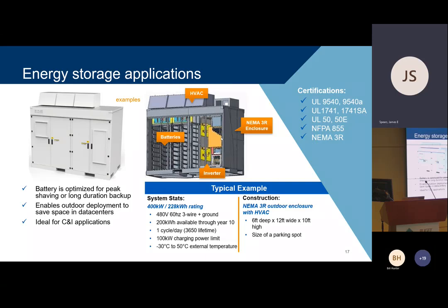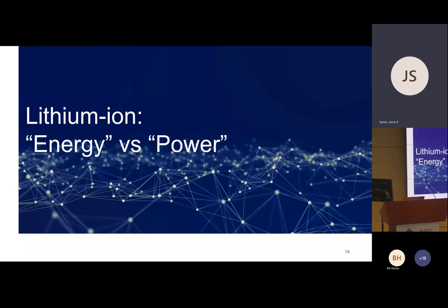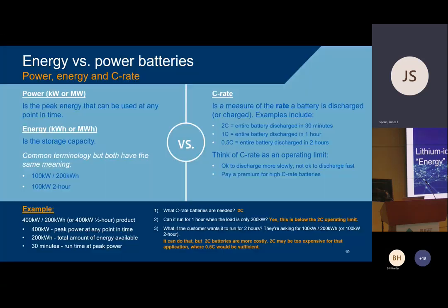So this is just one example of an energy storage application. Now I'm going to run through these next slides quickly because we don't have too much more time. This just basically shows in detail what the difference is between an energy battery and a power battery. Power batteries dump their power quickly, like in a UPS application. So a high C-rate battery, and by that I mean 5C or 6C, means that battery is designed and intended to dump all of its energy in 1/6 or 1/5 of an hour. So in between 10 and 12 minutes, that battery is set up to completely exhaust itself.